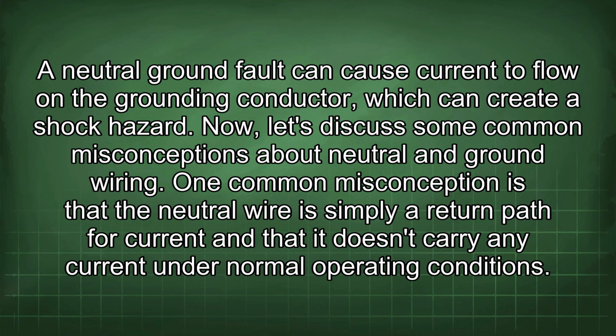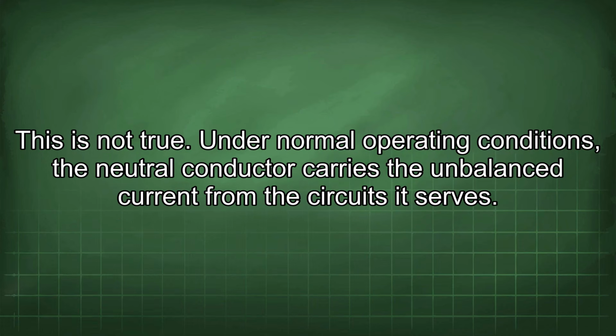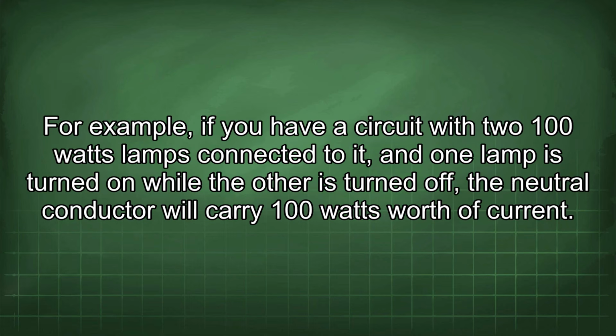Now let's discuss some common misconceptions about neutral and ground wiring. One common misconception is that the neutral wire is simply a return path for current and that it doesn't carry any current under normal operating conditions. This is not true. Under normal operating conditions, the neutral conductor carries the unbalanced current from the circuits it serves. For example, if you have a circuit with two 100 watt lamps connected to it, and one lamp is turned on while the other is turned off, the neutral conductor will carry 100 watts worth of current.